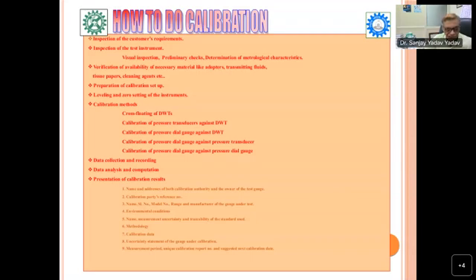You have to have all this information in the presentation of calibration result: the name and address of both the calibration authority and the owner of the test gauge, calibration party, reference number, serial number, model, manufacturer, environmental conditions, measurement uncertainty, and traceability of the standard. Then briefly the methodology, and then calibration data, uncertainty statement of the calibration, and then measurement period, unique calibration report number, and suggested next calibration due. You cannot force a due date on the user. You have to suggest the next calibration due date only.